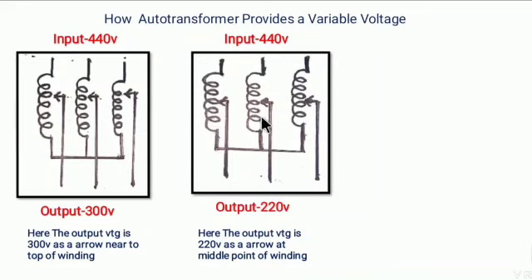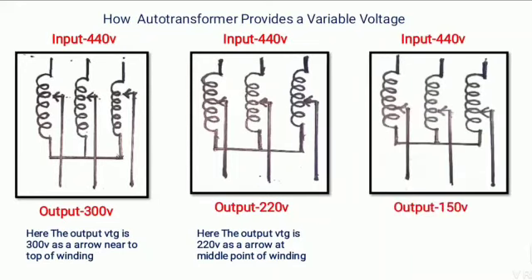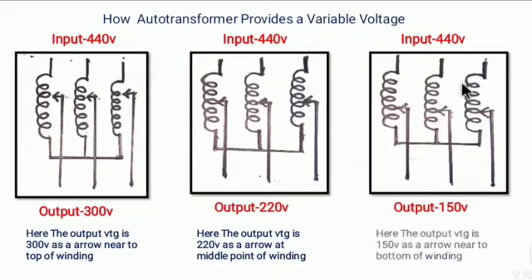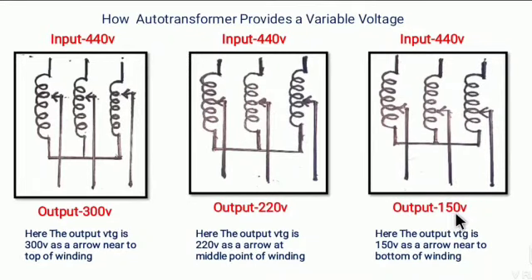The number of turns consumed by the secondary side is less compared to the previous diagram, therefore the output voltage is less. In the next diagram, the same input voltage of 440V is present. Here the movable contact is at the bottom of the winding, therefore the number of turns consumed by the secondary side is less compared to the previous one, and the output voltage is 150V.